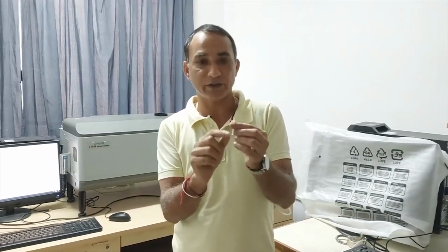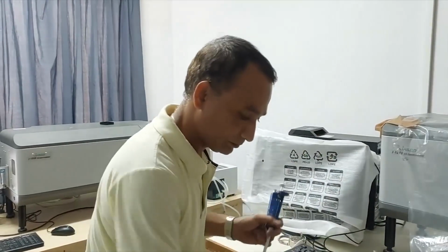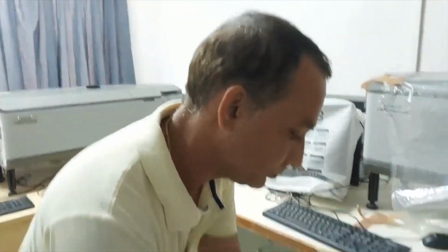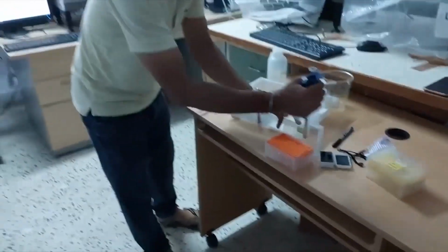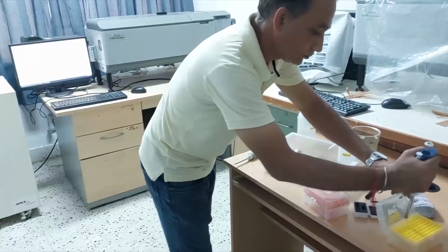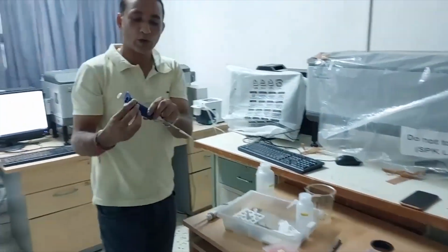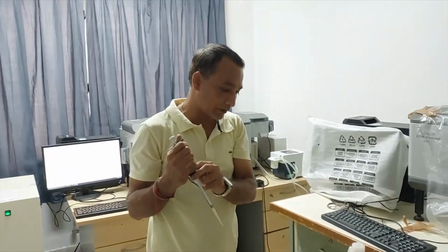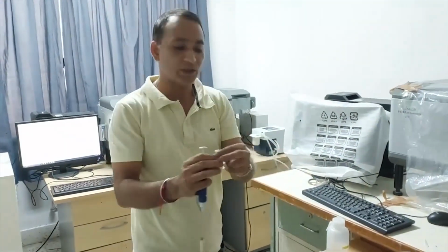We use a quartz cuvette because we are working in the UV region and we cannot use glass, as glass strongly absorbs the UV radiation. So this is the cuvette of 1 millimeter path length. I will now be adding the buffer or the solvent, whatever solvent we are using, in this cuvette. A 200 microliter volume is generally sufficient for recording. So I am taking 200 microliters of water for our experiment. This will be our blank.